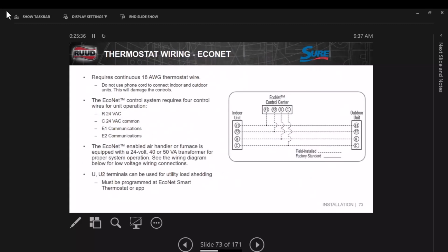Let's get into wiring the thermostat. This is what we just talked about a minute ago. We use just regular 18 gauge thermostat wire, just like you're used to using. Don't use anything like phone cord or 20 gauge wire or whatever. We want to use 18 gauge, real good thermostat wire. The Econet control system requires wires for operation: R, C, E1, and E2. If we've got it on a 24-volt system, then you're going to have to put in the other wires, and we'll talk about that in a minute.